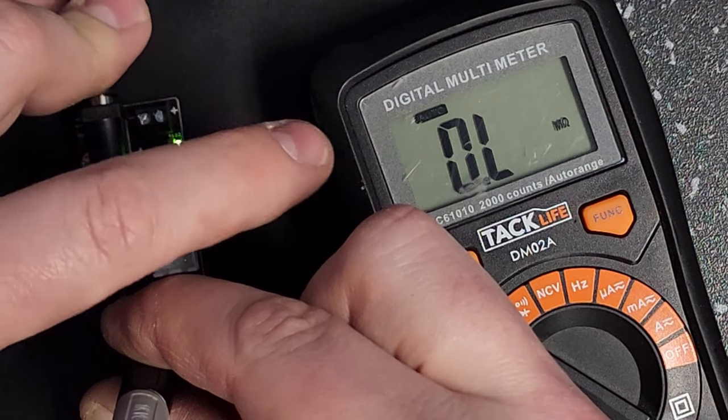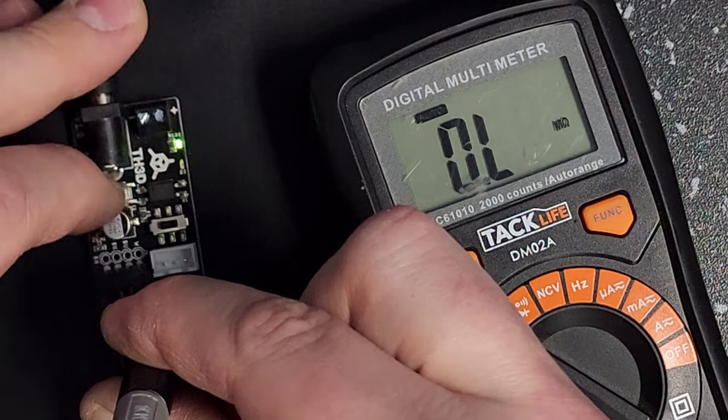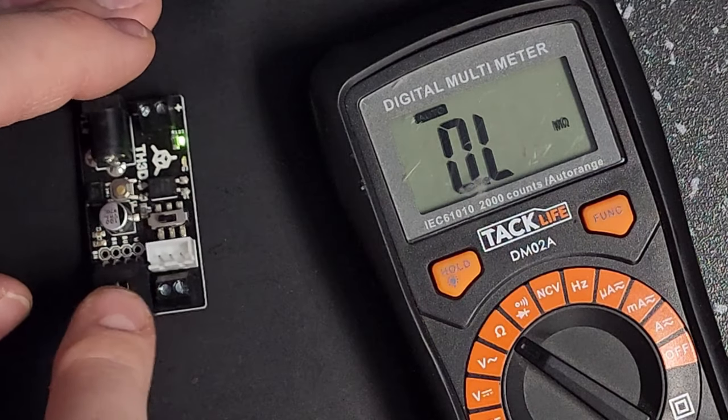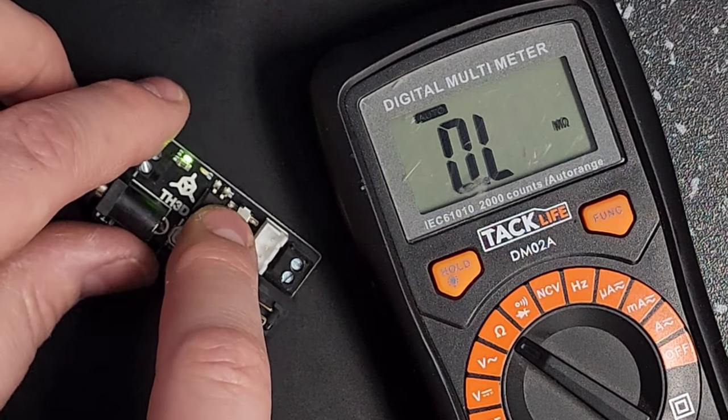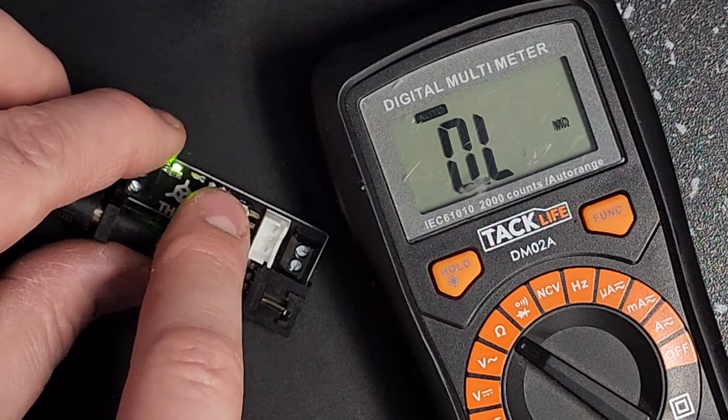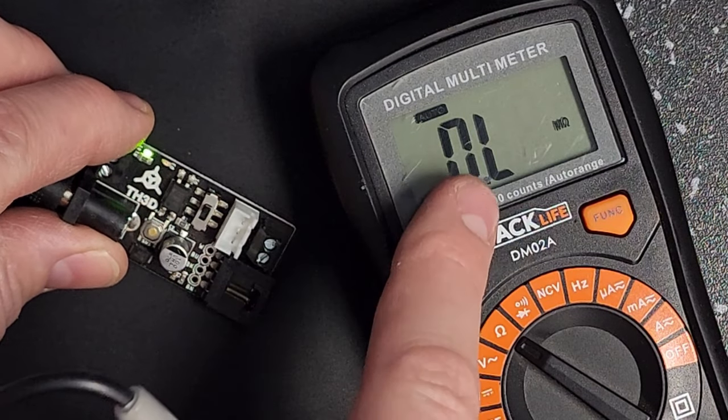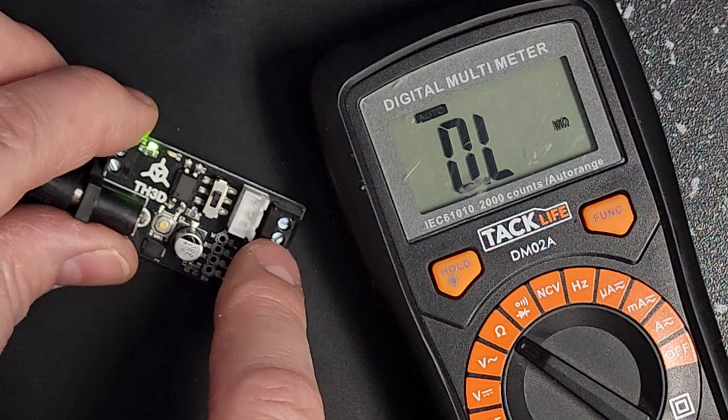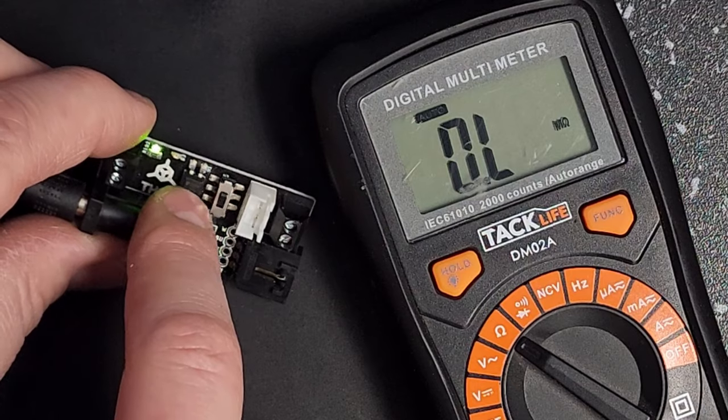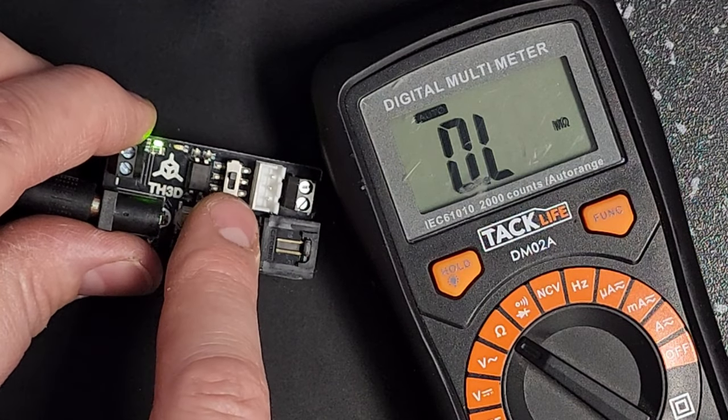It doesn't seem to care, so we know this board's working. Now if for some reason, regardless of what position you put this switch in, you're not getting any change here or it's thousands of ohms resistance, that means that this opto IC has failed and this board will need to be replaced.